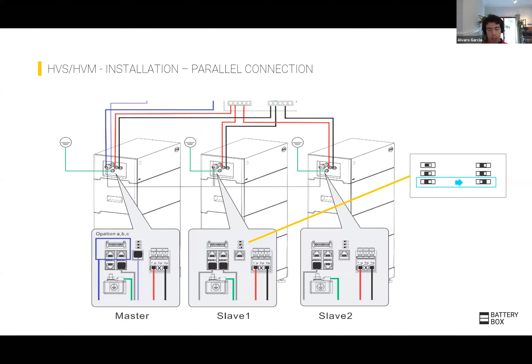Okay, and the final step is the commissioning. So in order to, it's very, very important to follow the right steps, because if not, the battery will not finish the commissioning process. The first thing is to switch on the battery. The inverter should not be on when you switch on the battery. So switch on the battery, do the commissioning.